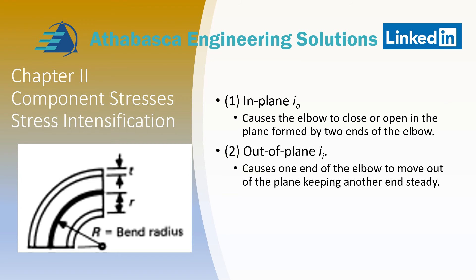In-plane stress causes the elbow to close or open in the plane formed by the two ends of the elbow. Out-of-plane stress is when one end of the elbow moves out of the plane while keeping the other end fixed. These values must be different because the pipe behaves differently — one loading is symmetric and the other is non-symmetric.